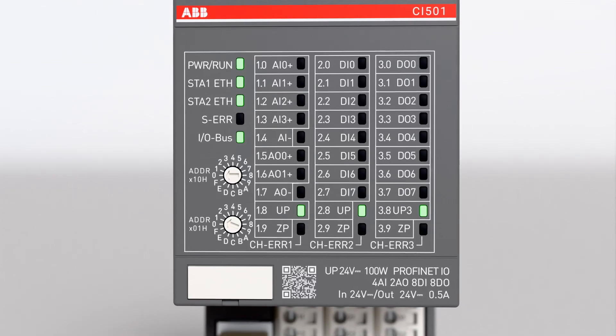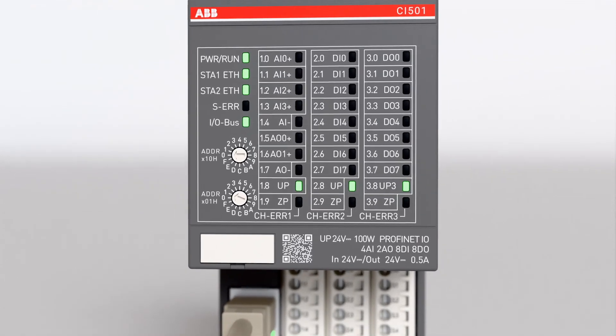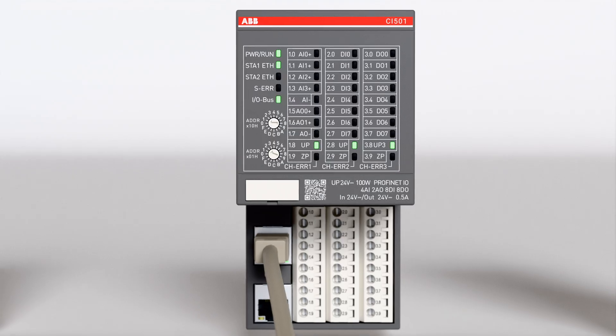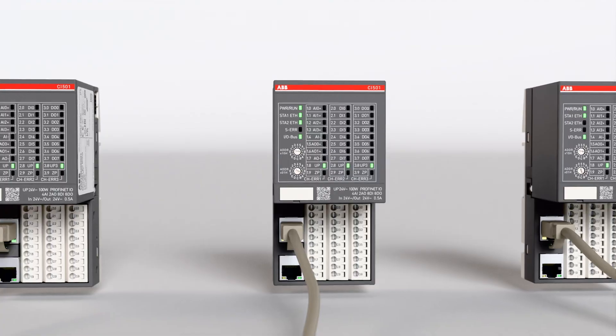On one hand, with IP configuration tool you can give device whatever name you want. On other, with rotary switches you don't need any tools in the first place, which makes replacement process way easier. And to finish with IP config tool, I'd like to draw your attention to this lonely blink button, which does exactly what it says: make STA2 LED on CI501 device blink three times. This could be useful if you have lots of devices and you want to locate the device you work with visually.